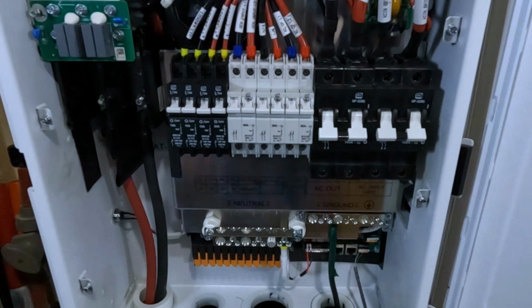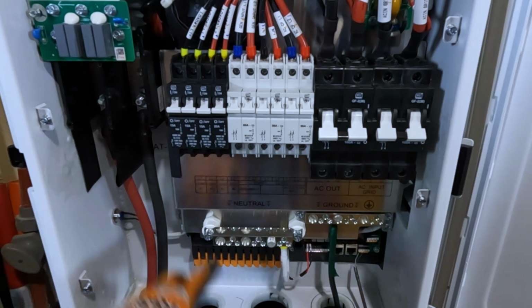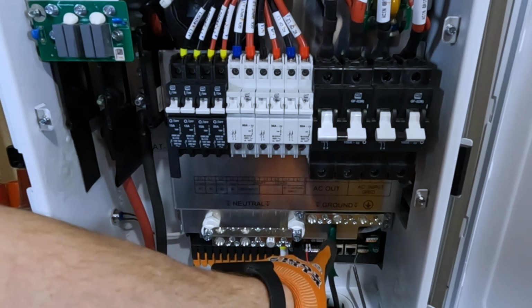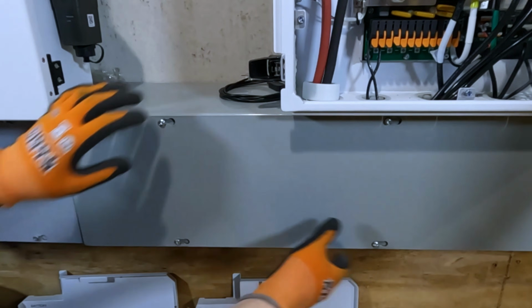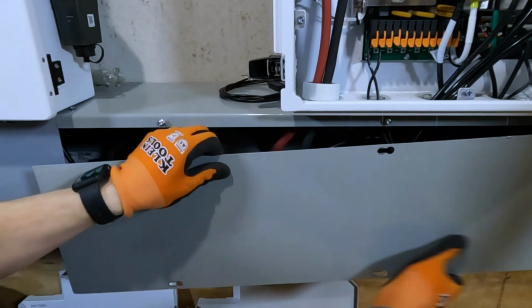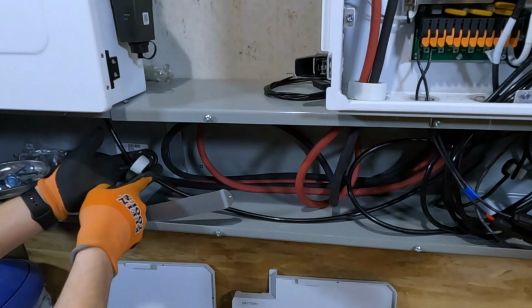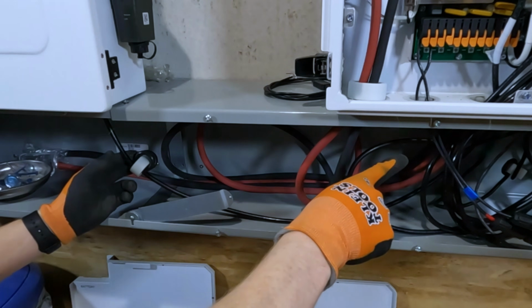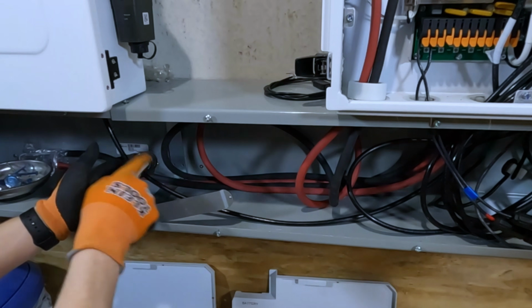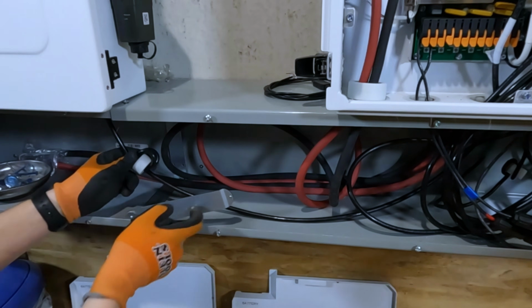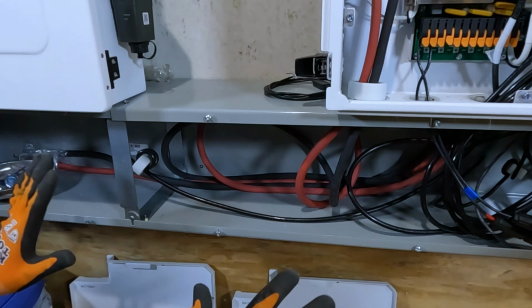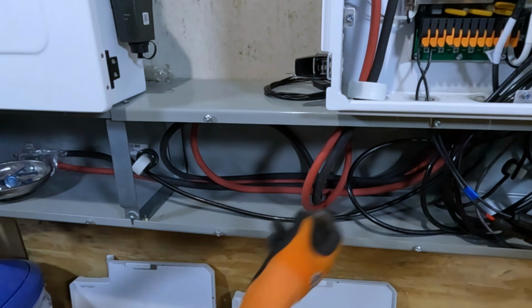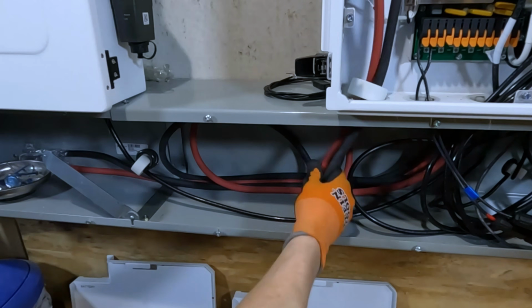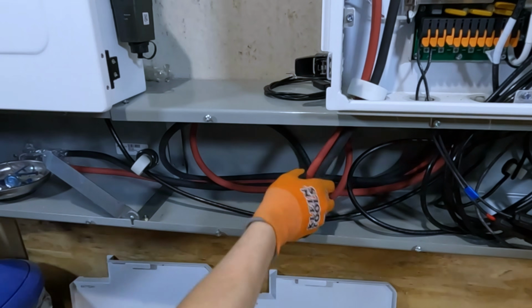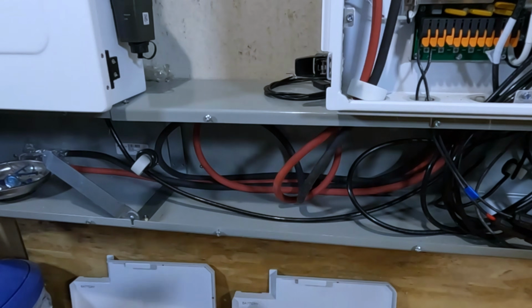Breakers are turned off. In the new inverter, we do have the battery connections already there, and I have my ground connection already in. If we open up the wireway, we can see, per the manual spec, we've got the ground line going to my grounding terminal in my wireway, and we've got the toroid wrapped twice around that line. But everything else still has to be hooked up. Your cabling does need to be the same length to make sure that everything is shared equally between the two inverters. So my battery cable length was measured. It's all the same length. That's why there's so much extra going to this inverter right now.